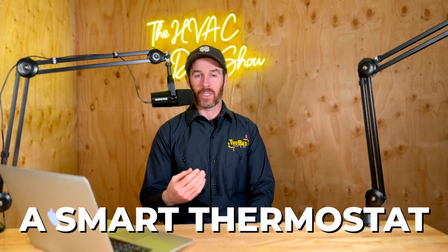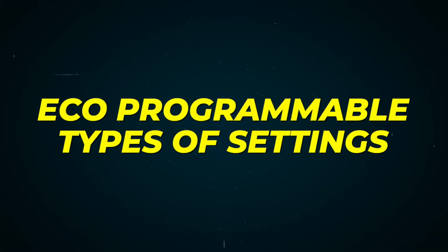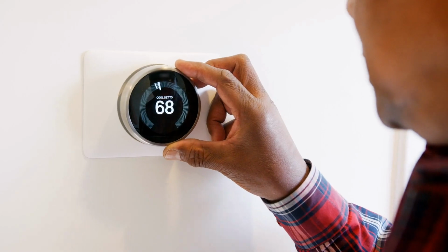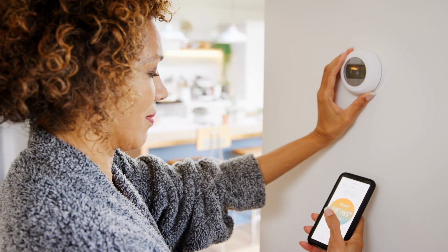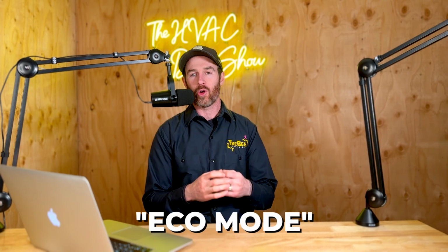Another thing to point out: if you're considering this system, they actually prefer a dumb thermostat, not a smart thermostat like an Ecobee or a Nest. If you want an Ecobee or a Nest, that's fine, they'll work with it, but there are features you'll want to turn off. The biggest one is any learning or eco-programmable setting where the thermostat takes over control because it thinks it knows better. That throws off how the system operates, since the thermostat tries to tell it what to do and can prevent the system from coming on for cooling because it's in eco mode, causing all sorts of weird issues.